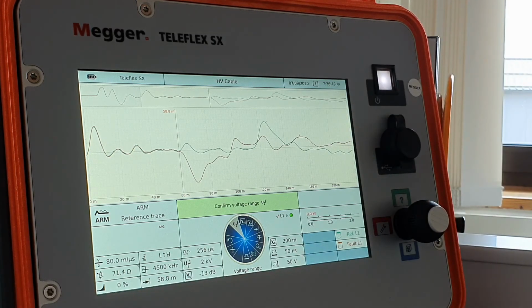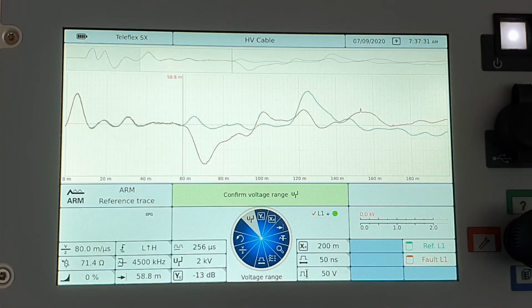I could superimpose a new measurement for comparison. On my screen, I see the most important data from my measurement out of history. It was taken with a 50 volt pulse of the TDR of 50 nanoseconds. A narrow pulse will give you more details. I was in the 200 meter range.